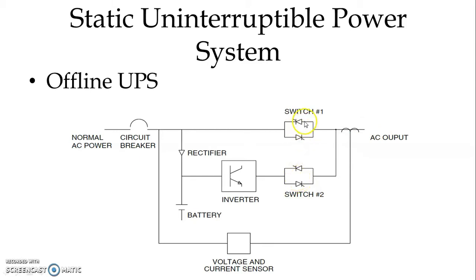Normally static switch number 1 remains on in case of offline UPS, and normal power is feeding the load. In case of loss of normal power, we have static switch 2, and we will supply AC power through the inverter to the load. We have voltage and current sensing. So in case of either total loss of normal power, or in case voltage falls below certain predetermined values, then we can have a switchover.